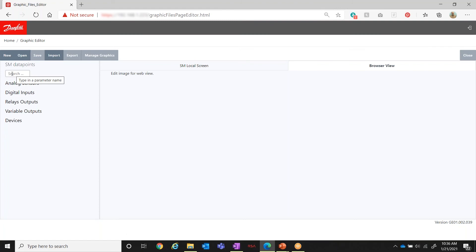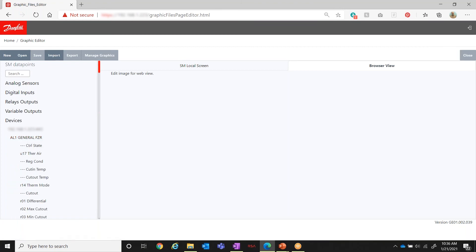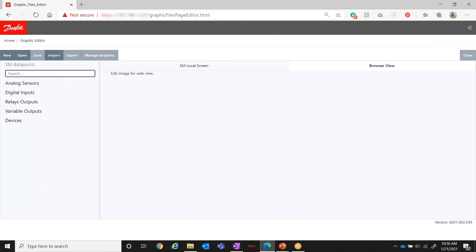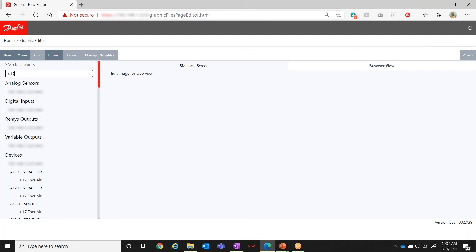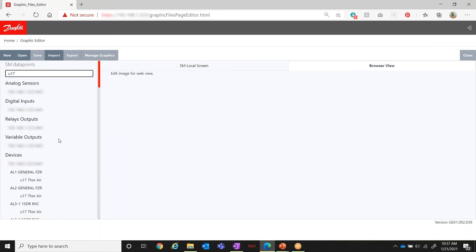One more thing to highlight: when working with a case controller there can be many, many data points — that can be overwhelming. The main temperature read is going to be U17. The best way to manage that is to use the search field and type in U17. Now you can go to each of the case controllers and see only U17 available. This is a very effective way to use the search option to narrow down the points you want to overlay.